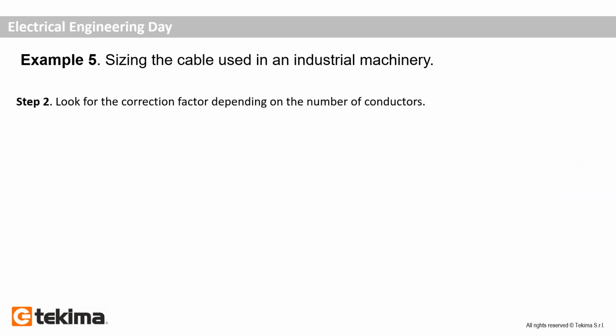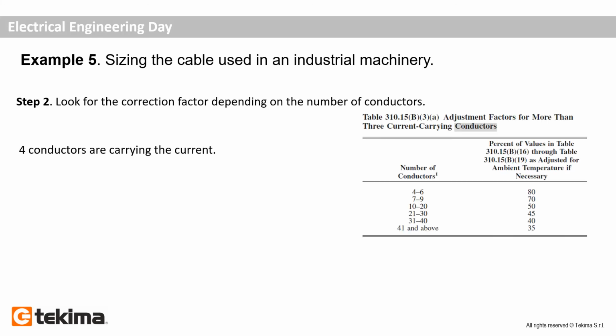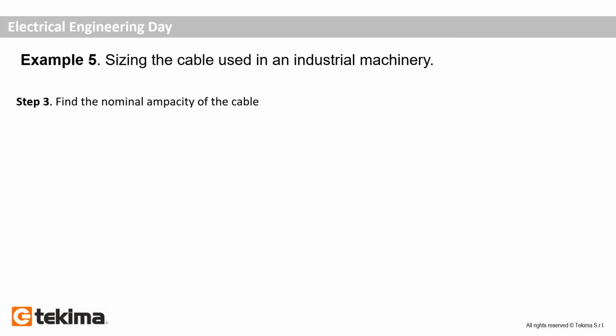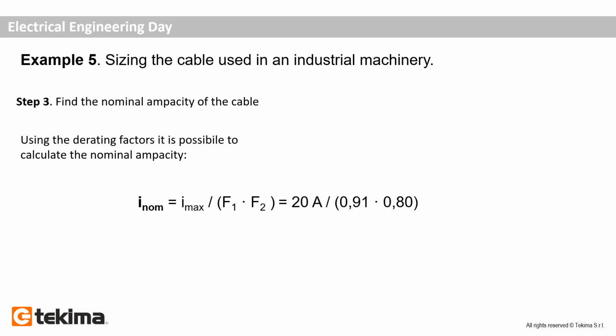The second step is to define the correction factor depending on the number of conductors, exactly like we have done in the previous examples. In this case, we have 4 conductors carrying the current, 1 is the ground, so in this case the correction factor will be 0.8. Step 3. Find the nominal ampacity of the cable. To understand the nominal ampacity of the cable, we have to divide the working ampacity of the cable by the derating factors. So we have 20 amperes divided by 0.91 and divided by 0.80, which gives 27.5 amperes.